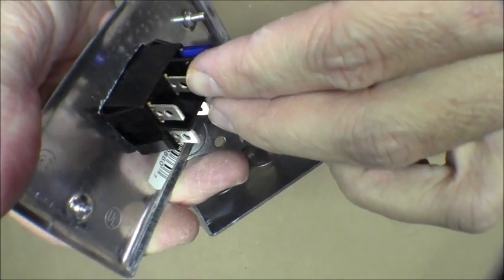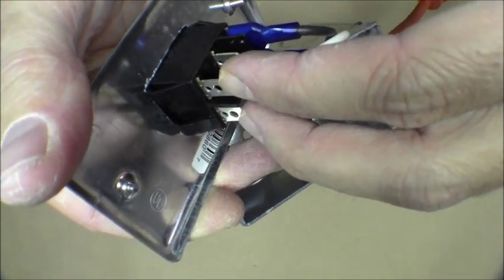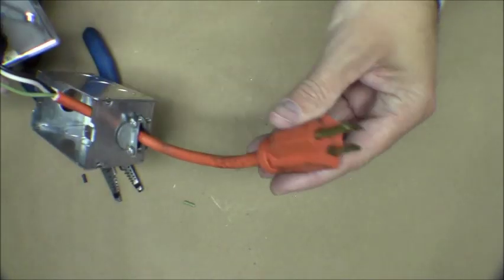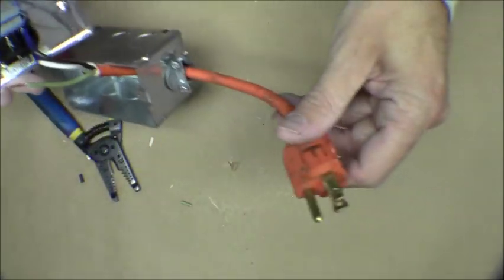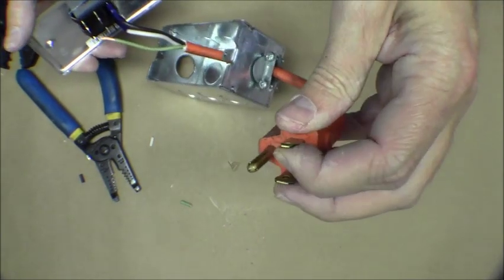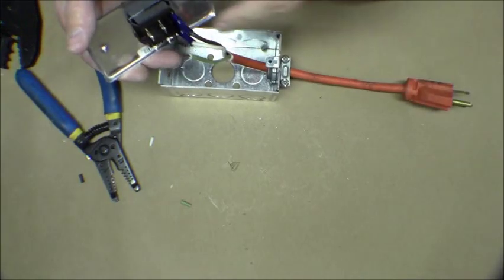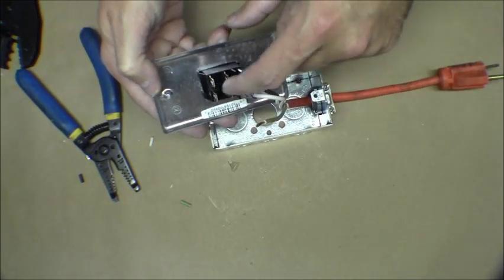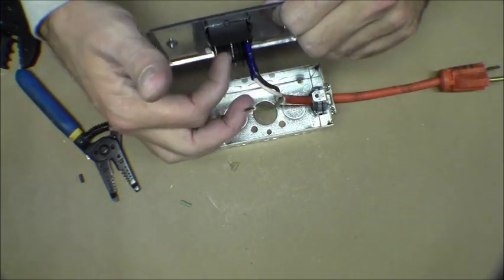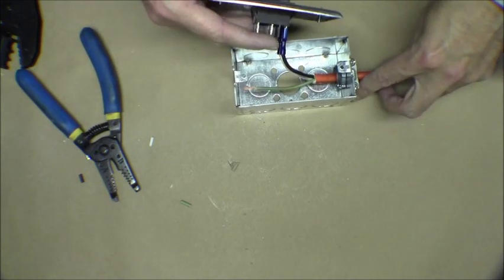Like I said, the center one will do the same thing with wires going to our furnace. And then with the top ones, this will be our incoming power. We got our female plug coming off there, and there will be no way that this, our male plug, that this would ever have power coming off of it. Because this double pole break before make, it breaks the poles and the center position is off.